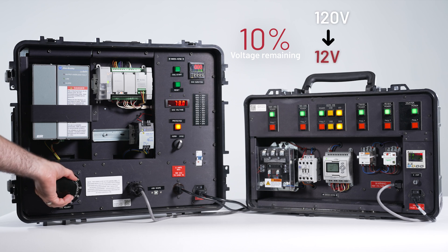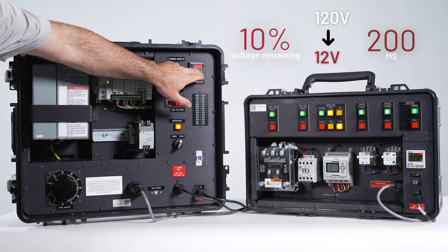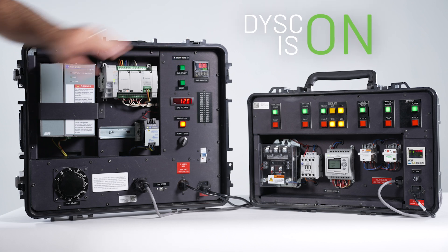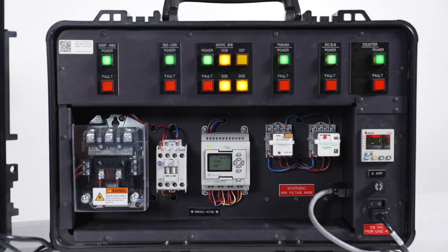Next, we'll configure the serious voltage sag that reaches 10% voltage remaining for 200 milliseconds. Let's run the simulation. With the DYSC protection, there was no unexpected equipment shutdown during this harsh voltage sag.